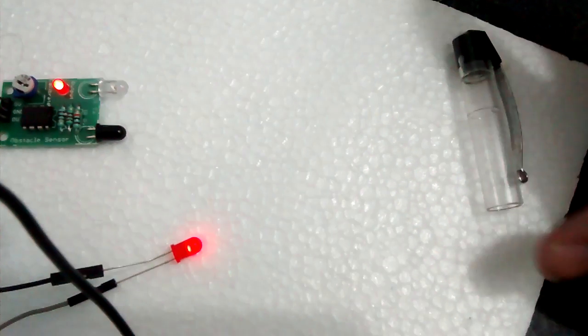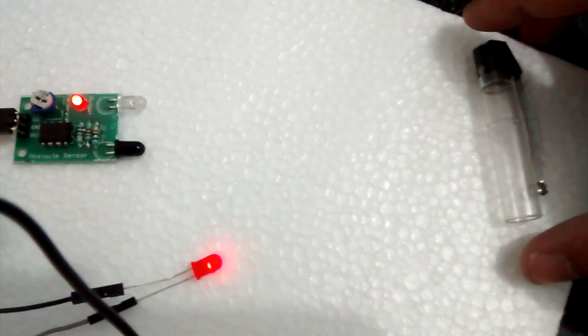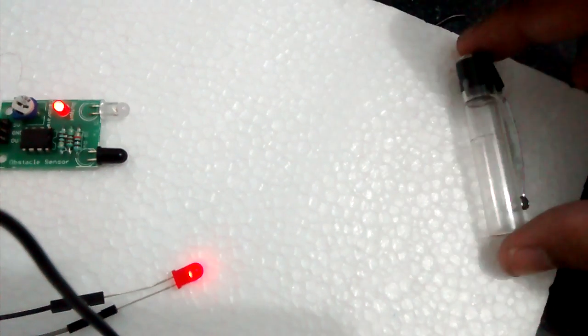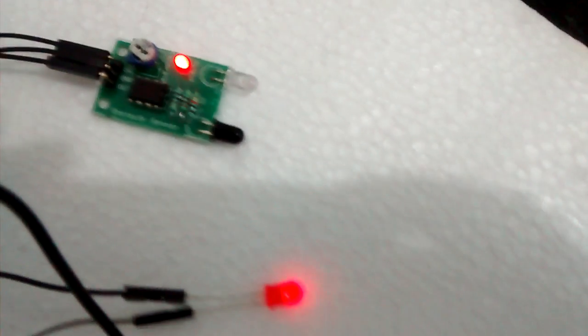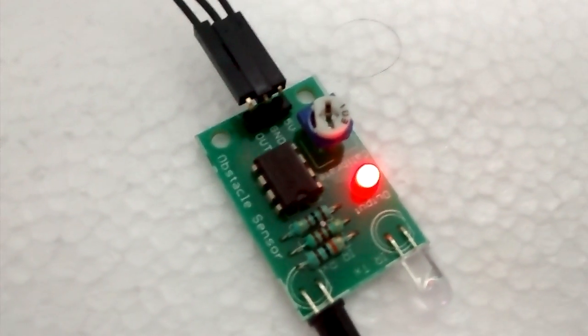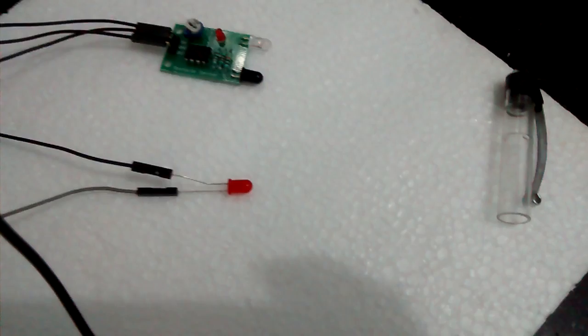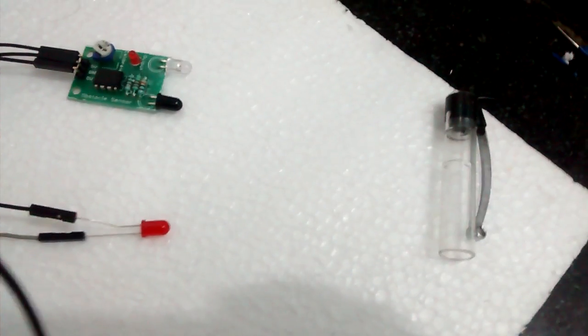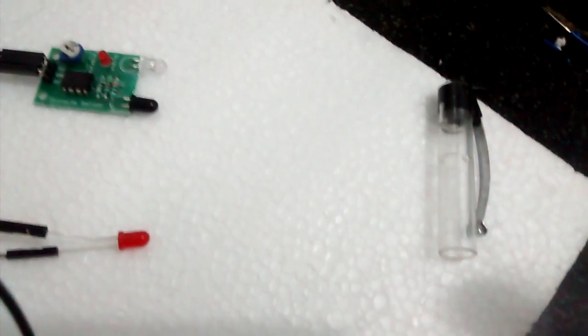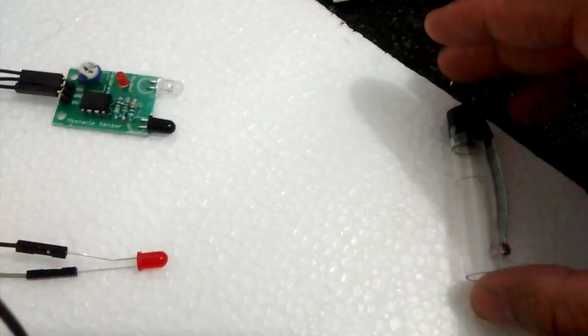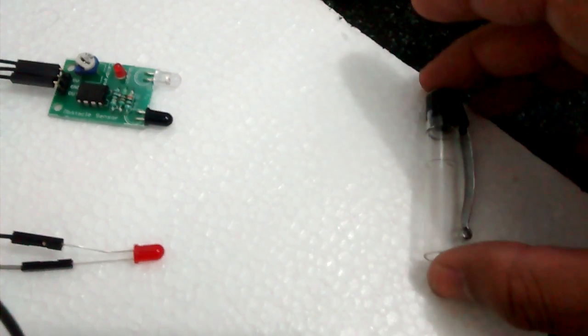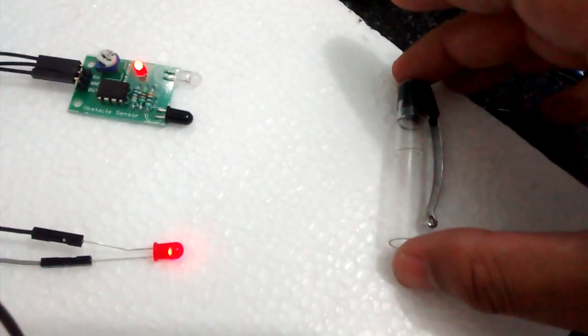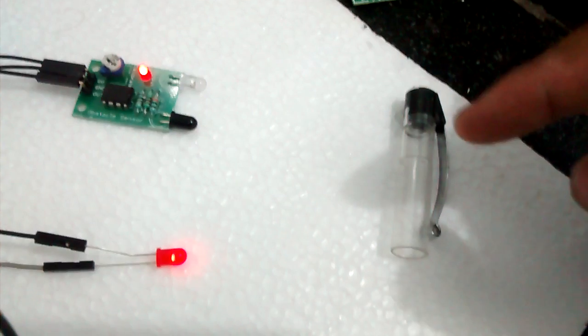If I remove this, it's not there, but when I keep it back, it's getting sensed. Now let's calibrate this. I'll turn this knob a bit. Earlier it was sensing the cap at this position, now it's not sensing. I'm moving the cap forward—now it's getting sensed. I just calibrated the sensor so that the distance got reduced.